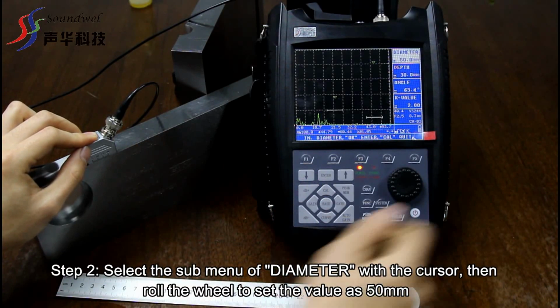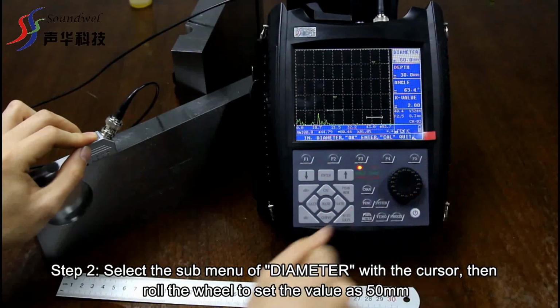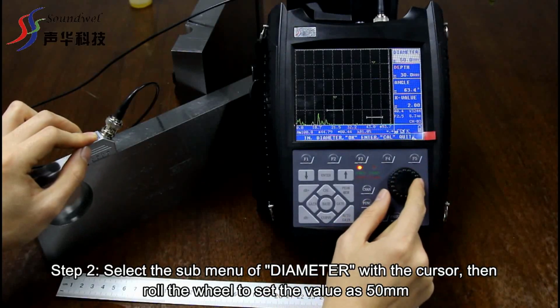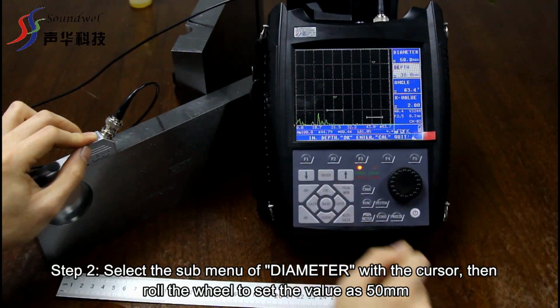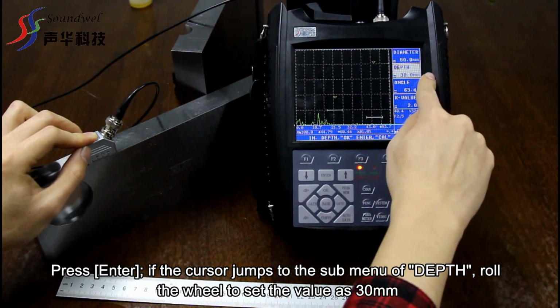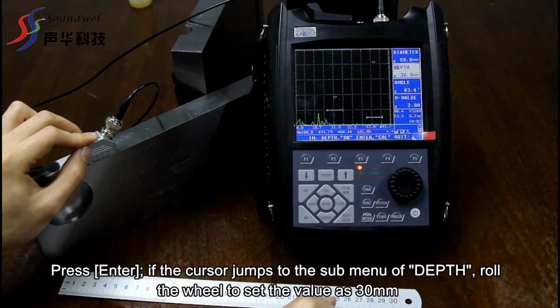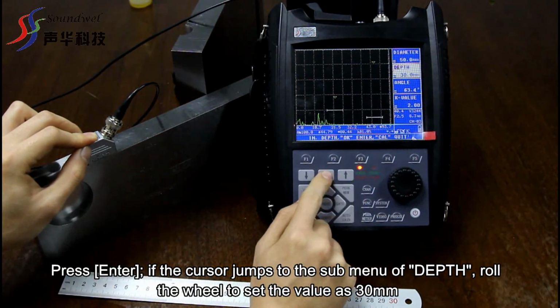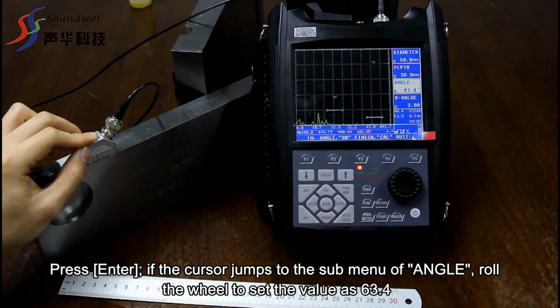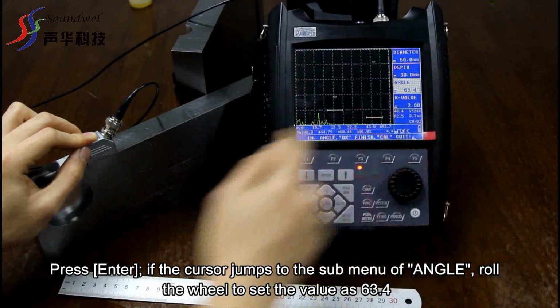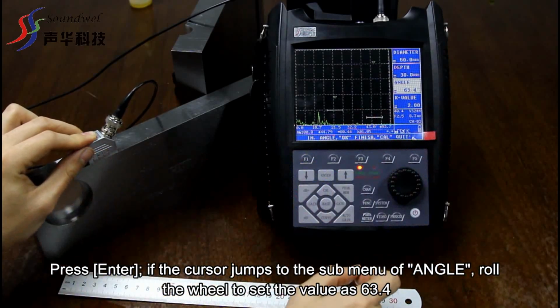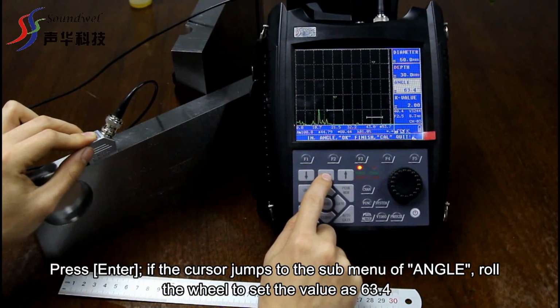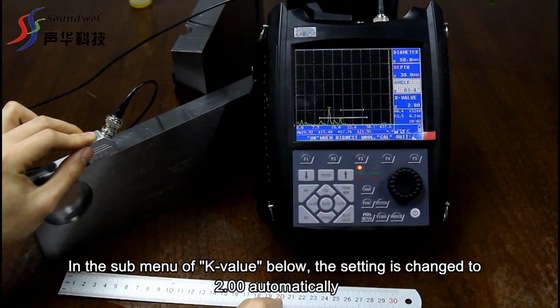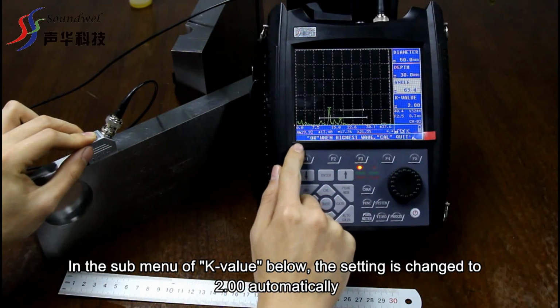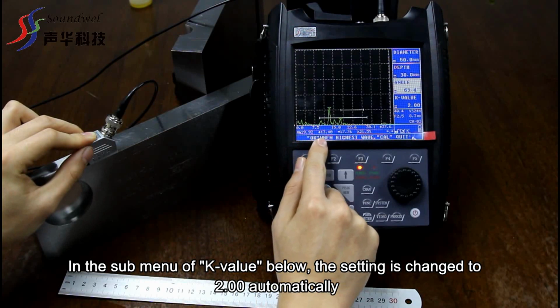Step 2. Select the submenu of Diameter with the cursor. Then roll the wheel to set the value as 50 millimeters. Press Enter if the cursor jumps to the submenu of Depth. Roll the wheel to set the value as 30 millimeters. Press Enter if the cursor jumps to the submenu of Angle. Roll the wheel to set the value as 63.4. In the submenu of K value below, the setting is changed to 2.00 automatically.